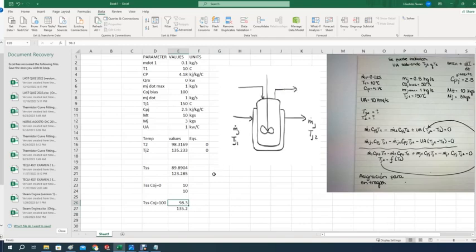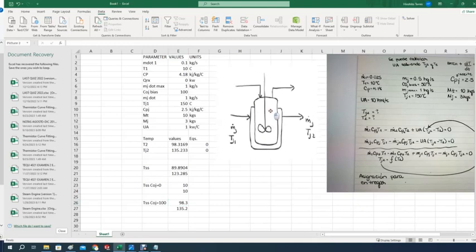So we can set a set point between 10 and 98.3, and the control system will properly adjust the valve as required if you have the proper tuning parameters. It is clear that for this system we should use a PI controller, a proportional integral controller, because this system will auto regulate without any problem, so it behaves nicely. So you better use a PI type of controller.